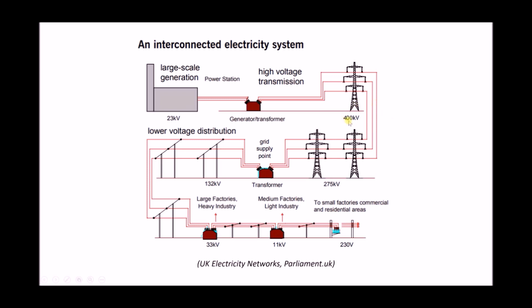The transmission network can range anywhere between 400 kilovolts and around 275 kilovolts, depending largely on the distances being covered. When we move closer to towns or built-up areas we step that voltage down to around 132 kilovolts. This is the grid supply point — the point where ownership of the network switches. The 400 kV and 275 kV side is the transmission network, owned and maintained by the National Grid. Once we step down to 132 kilovolts we're into the distribution network, and ownership and control belongs to distribution network operators.